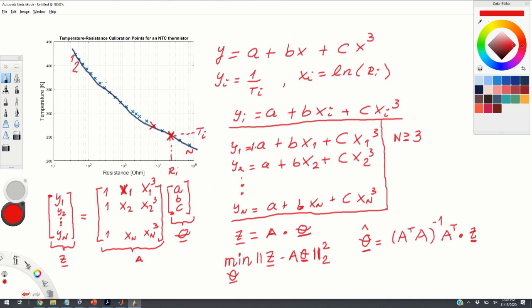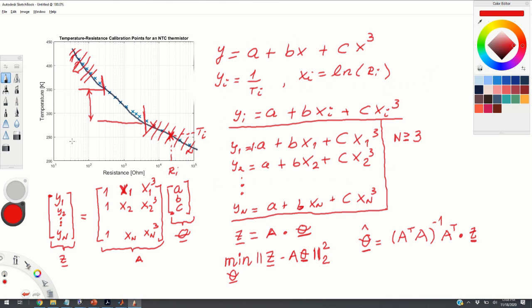Another thing to keep in mind: if you expect the temperature to fall within a certain interval, it's better to disregard points outside that interval and only use data within that range to form the equations. From my experience, your results will not be accurate if you use all the points when your expected temperature range is only a subset — you will introduce errors.